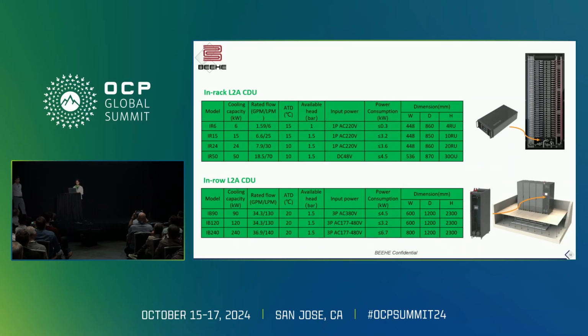We also have sidecar, as well as in-rack liquid-to-liquid and in-rack liquid-to-air CDUs for the ORV3 MGX racks. Our CDU design has redundancy, and components such as pumps are hot swappable. We also provide real-time monitoring on pressure and coolant quality, including resistance, purity, and conductivity, with automatic alerting when any anomalies are detected.